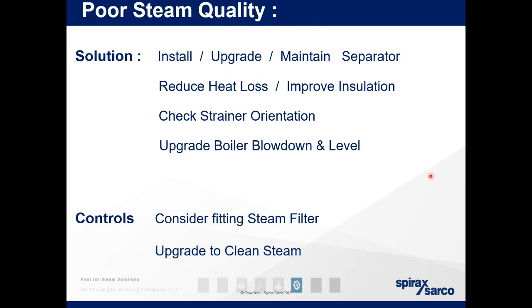So as it says here with controls, consider fitting steam filters, upgrade to clean steam. If you have a process where steam is injected directly to process or to product, the minimum grade should be filtered steam because of the human consumption element. So we would recommend the upgrade to either clean steam or filtered steam, depending on your process.